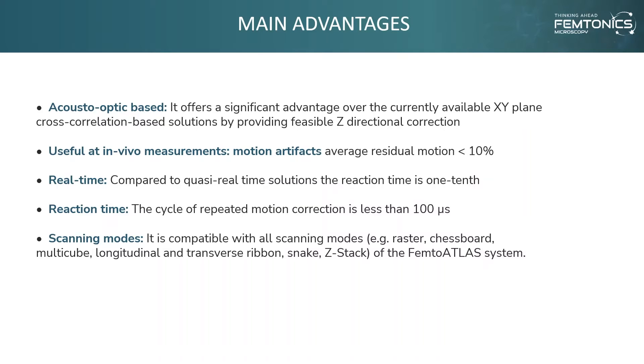As a summary, let's see the main advantages of Femtonics Focus Spinner. It is acousto-optic-based, so by leveraging the capabilities of 3D random access line scanning, our system enables seamless motion correction along each axis. It offers a significant advantage over currently available XY-plane cross-correlation-based solutions by providing feasible Z-directional correction. It is useful for in vivo measurements — motion artifacts caused by respiratory movement or heartbeat can be efficiently eliminated, with an average residual motion under 10% of the original motion. It is real-time: during the measurement, the focal point is online-relocated based on the estimated motion of the reference point. Compared to quasi-real-time solutions, the reaction time is one-tenth. The cycle of repeated motion correction is less than 100 microseconds, meaning the largest residual motion amplitude is the one collected during this short time window.